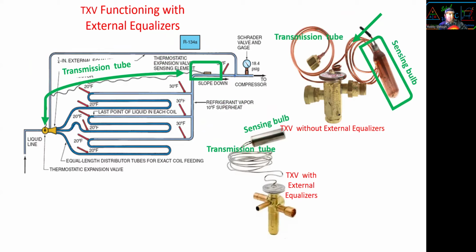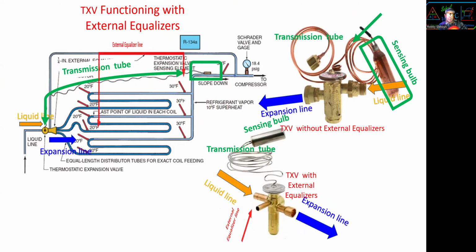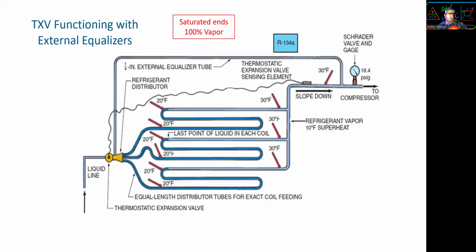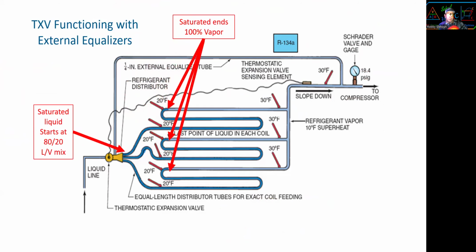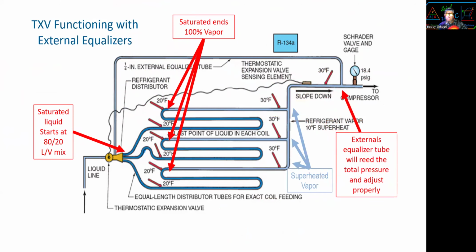Remember, we have the sensing bulb transmission tube on the TXV, and the suction and the transmission line. That's what's important. Now, saturated liquid starts, saturated vapor ends, correct? At the end of boiling, superheated vapor right here. We have superheated vapor, 10 degrees. The external equalizer will read the total pressure and adjust properly. That's why we have it, because we have 3 multi-evaporators. Suction line temperature minus boiling point equals superheat. In this case, it's 10 degree superheat.